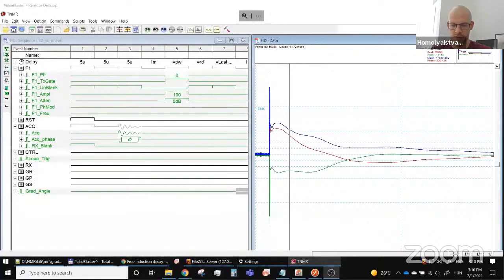We can see the result of this measurement for the pulse and the resulting FID on the right side of the screen and the pulse sequence on the left. On the right side, you can see both the pulse and the decay that follows. On the left side, you can see the 90-degree pulse and the receiving sequence.